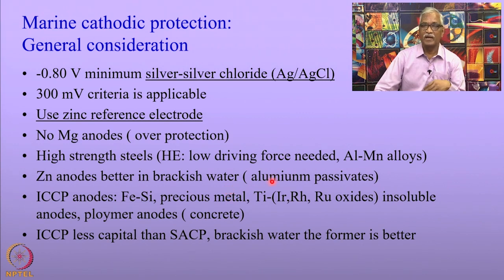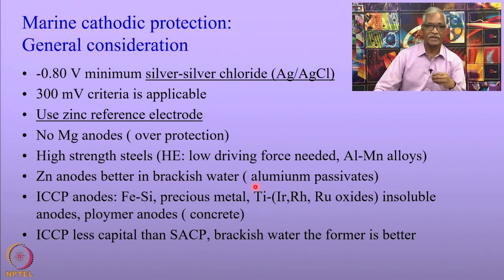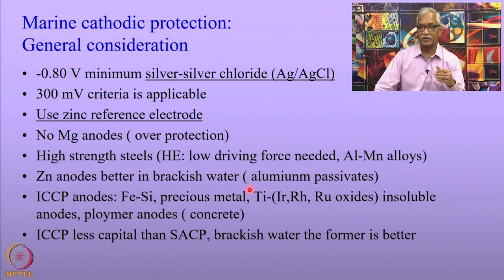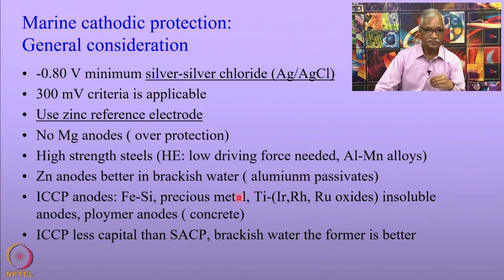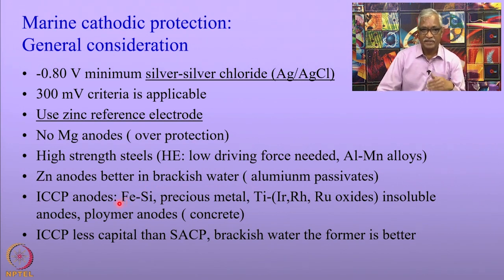Zinc anodes are better in brackish water as aluminum passivates. For aluminum to act as a sacrificial anode, the presence of chlorides is necessary — when chloride levels are low, aluminum anodes passivate. For marine structures, both ICCP and sacrificial anode systems are used.